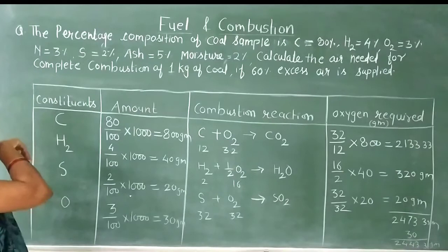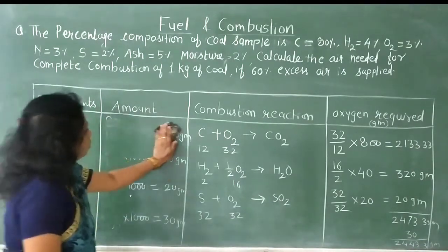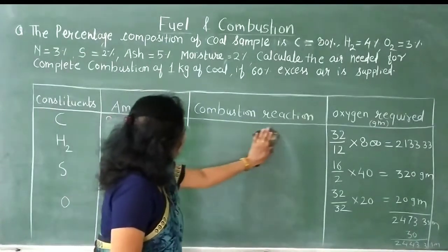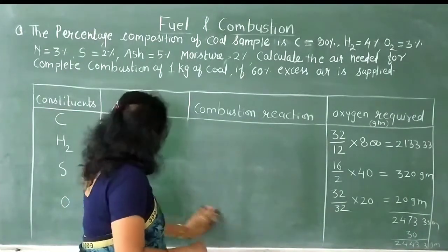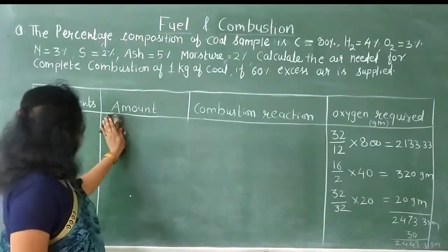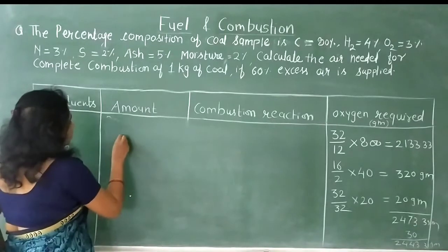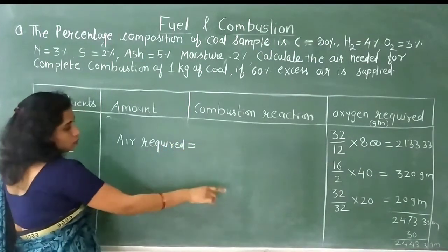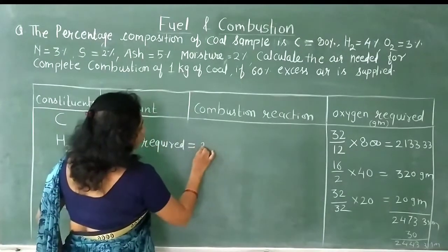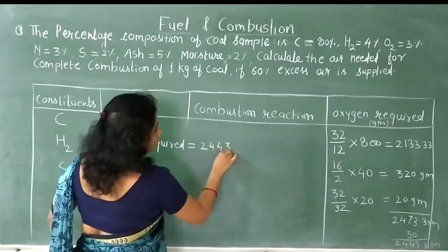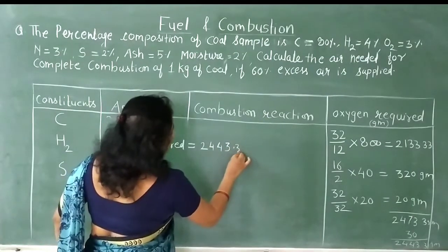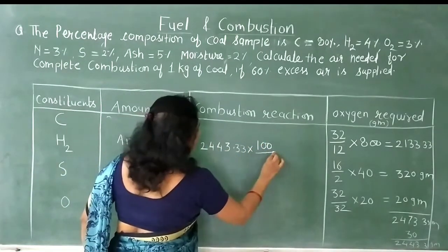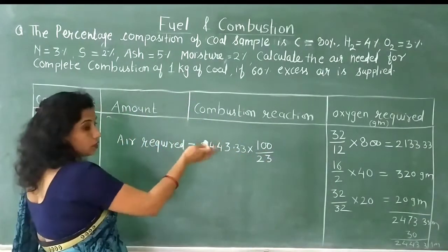Now we need to find the air required. The formula is based on the fact that by weight, oxygen is 23% present in air. So: Air Required = Oxygen Required × (100/23) = 2443.33 × (100/23).